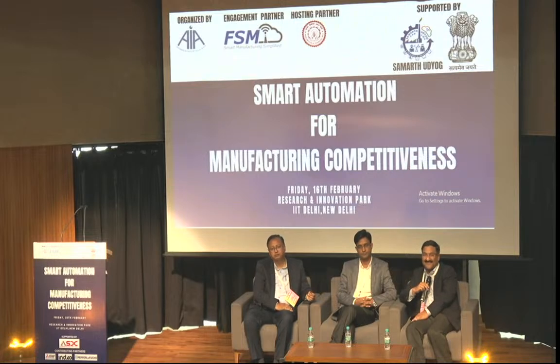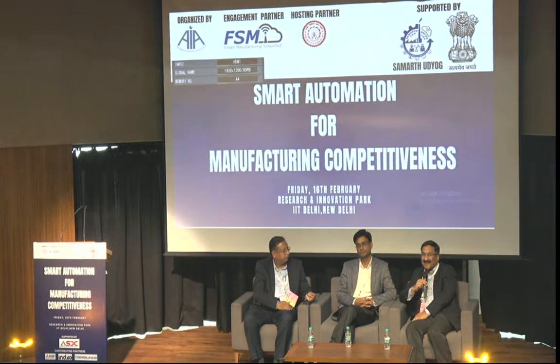Sir, that's what the question was. If we can replicate the whole part digitally, then rather than keeping multiple sensors, we could take 1 or 2 sensors at a critical location, since we have a digital replica of the whole machine. For example, for a motor, if we take output from one sensor, that should be reflected and visible in our digital replica. So our usage of sensors may decrease a little, and we can implement this at each location for each machine separately. By experience, I can tell you one sensor wouldn't suffice, because a minimum of 2 dimensions with defined amplitude are necessary for any kind of preventive maintenance related to vibration.